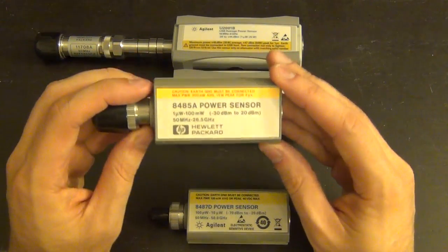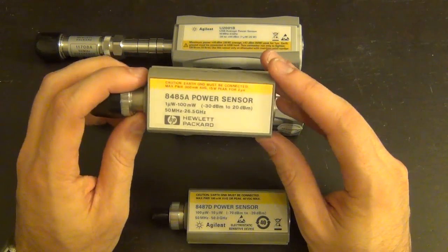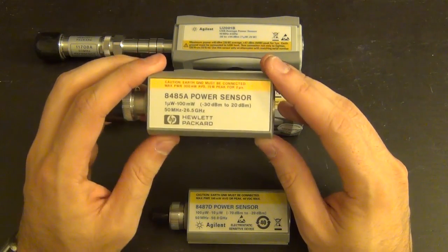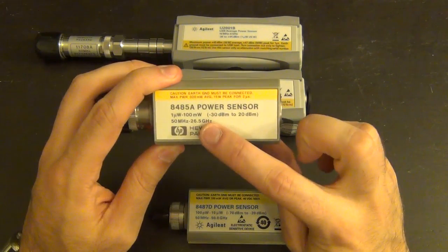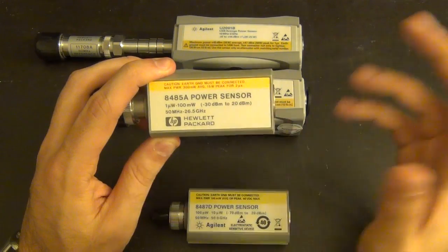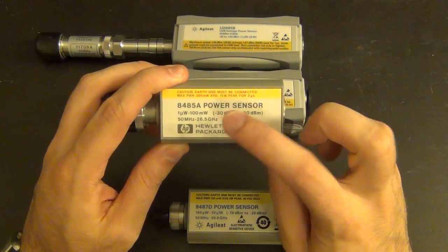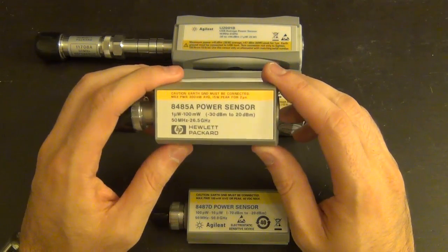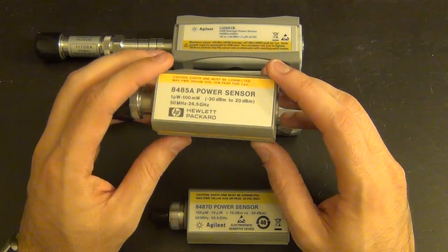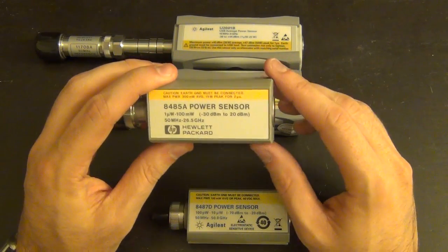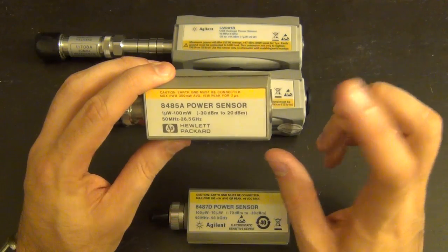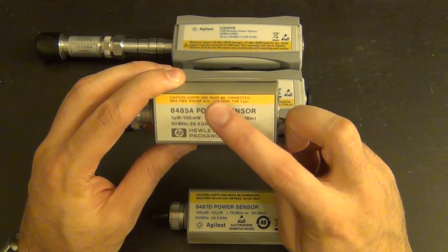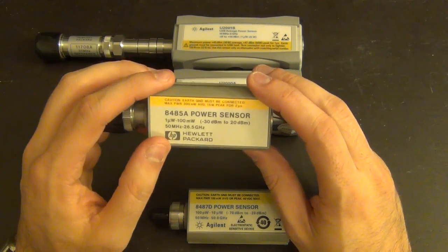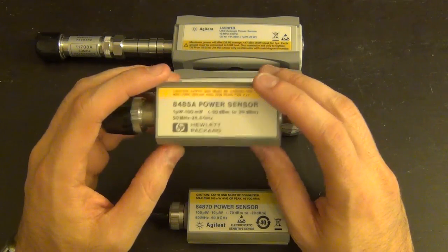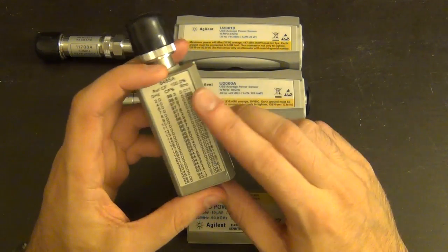This is a fairly old sensor, the 8485A, a very popular model. It's a medium power sensor, working from minus 30 dBm to 20 dBm. Below minus 30 is below the noise floor of this model, and above 20 dBm would be above its linearity level. It will get damaged if you put more than 300 milliwatts into it. It works from 50 megahertz to 26.5 gigahertz.